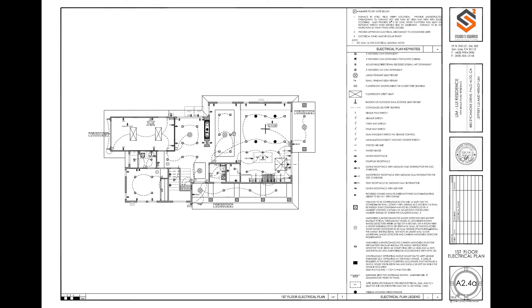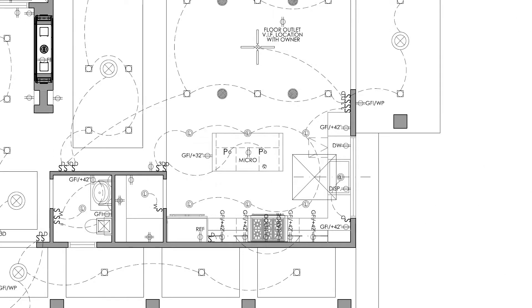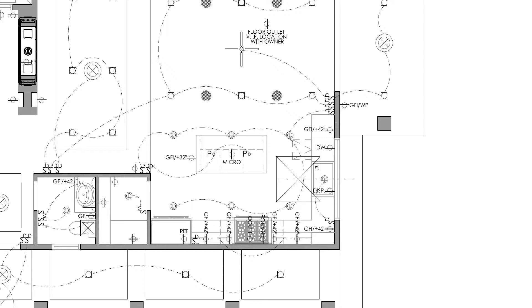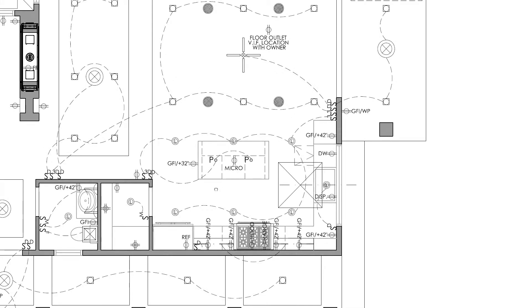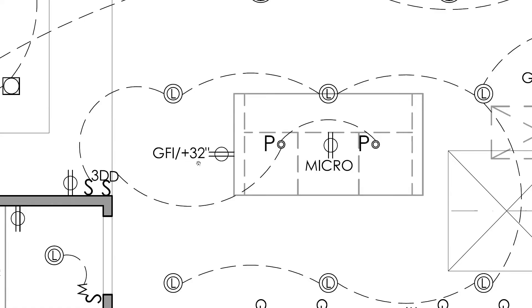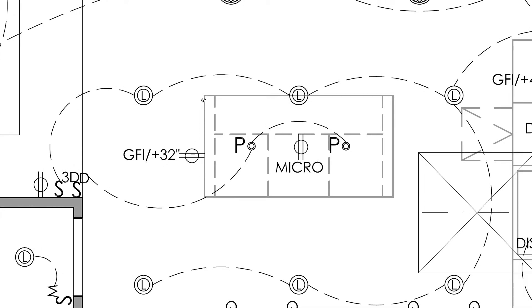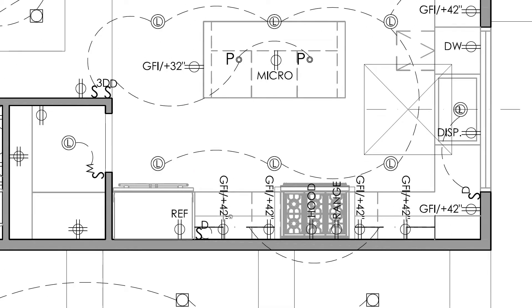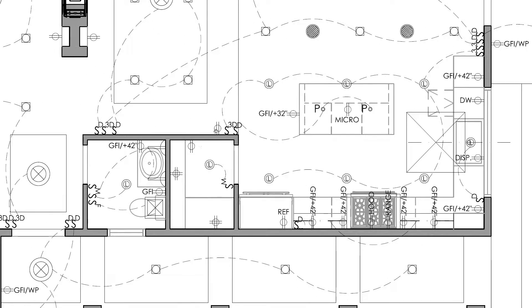Other important elements shown on the electrical plans are labels. For example, in the kitchen we have abbreviations for the microwave, washer, disposal, range, hood, refrigerator, and others. We will also show height labels — for example, a label saying 'plus 32 inches' means that outlet on the island will be placed at 32 inches high. Outlets over the counter will be placed at 42 inches high. If no height is specified, outlets will be placed at the standard height of 10 to 12 inches.